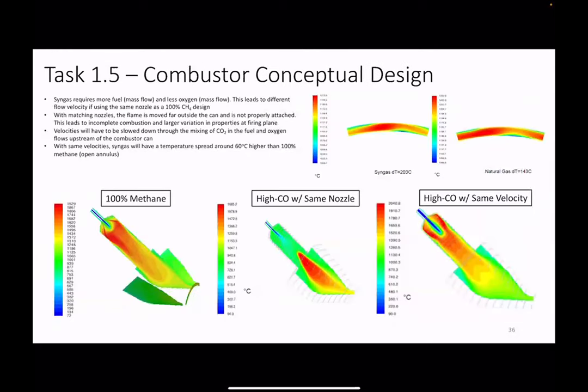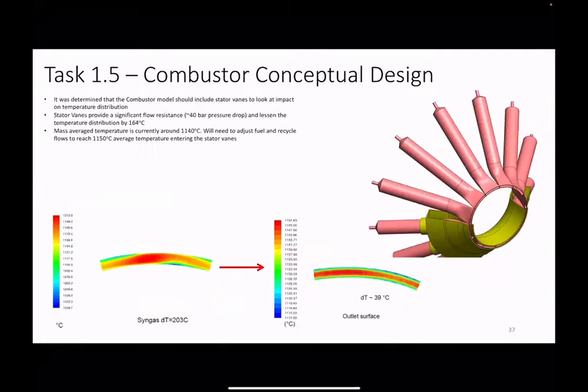In addition to the case design, we also moved forward with combustor design, mainly looking at adjusting the fuel flows. We started with our 100% methane design, then looked at the impact of changing to the required fuel and oxygen conditions for a high CO syngas. In the middle bottom image, you can see the flame is well downstream of the can, resulting in incomplete combustion. We realized we have to maintain the same flow velocities going into the combustor can to get similar performance, as shown comparing the left and right images. The question is how you develop a control system for that, and how you get a more uniform temperature distribution going into the turbine flow path.